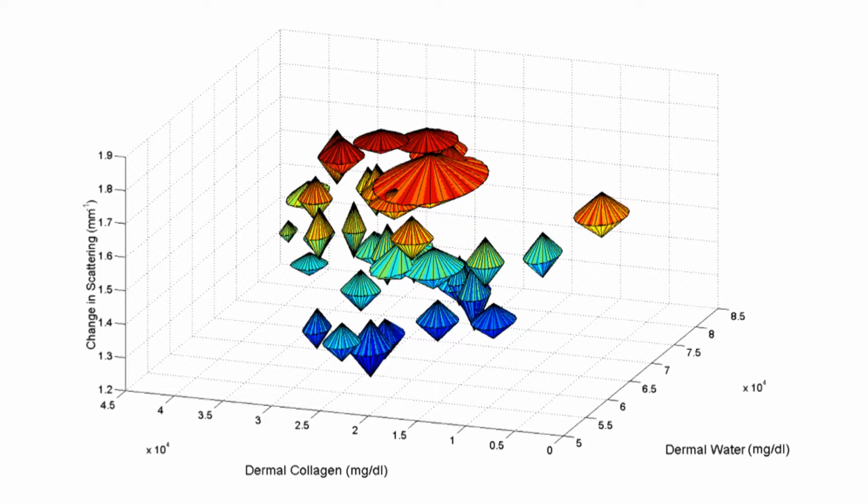Each object in the figure is a subject observed over a 1-month period. Typically, an individual occupies a moderately defined space with some variance, while the different individuals measured are clearly discrete. These differences between people and over time cause path length distribution differences that result in errors in the Beer's law calculations. These path changes are the dominant error in non-invasive glucose measurement.